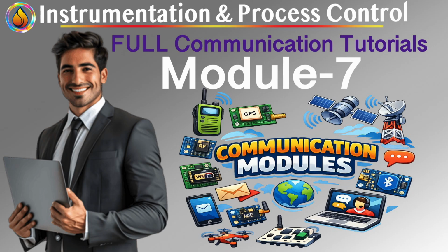In traditional DCS and PLC systems, sensors measure, controllers decide, actuators act. The field devices are mostly obedient messengers. Foundation Fieldbus flips this model. Field devices become intelligent, executable, cooperative. Transmitters can host function blocks. Valves can host function blocks. PID loops can execute in the field. The tutorial states this clearly: by using function blocks, Foundation Fieldbus attempts to move control right down to the field level, eliminating the need for a central controller for many functions. That's not incremental. That's architectural rebellion.